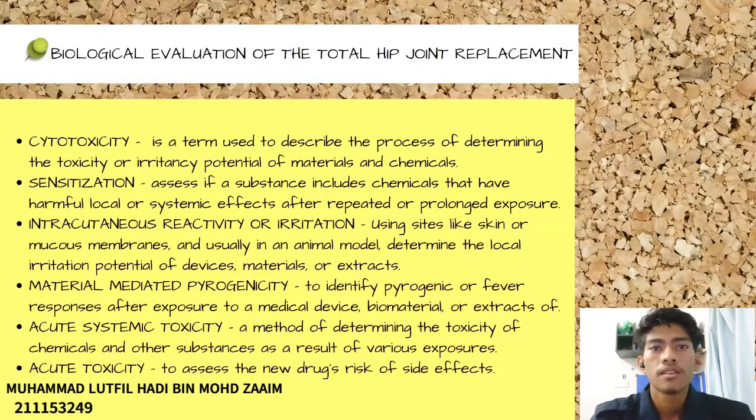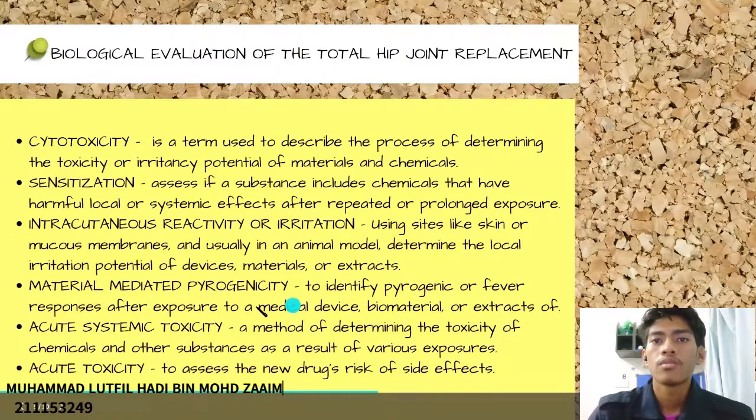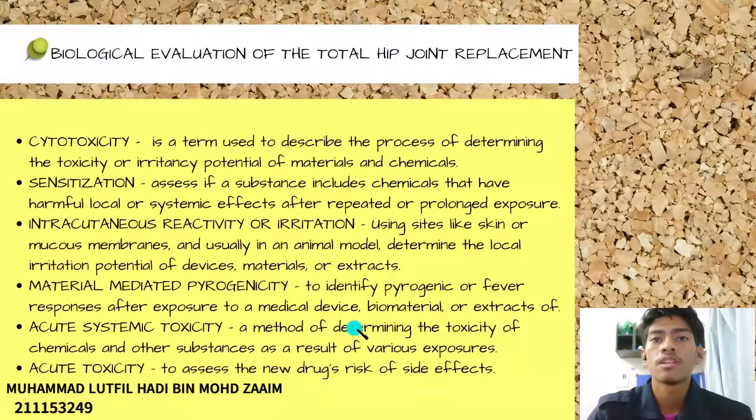For long-term implants: first, cytotoxicity is a term used to describe the process of determining the toxicity or irritancy potential of materials and chemicals. Second, sensitization: assess if a substance includes chemicals that have harmful local or systemic effects after repeated or prolonged exposure. Third, intracutaneous reactivity or irritation: using sites like skin or mucous membranes, usually in an animal model, determine the local irritation potential of device materials or extracts. Fourth, material-mediated pyrogenicity, to identify the pyrogenic fever response after exposure to a medical device, biomaterials or extracts.